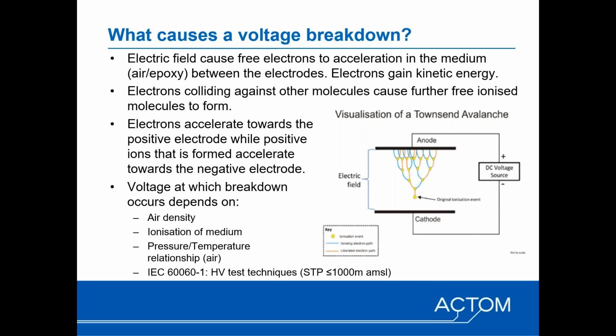Another factor that influences the voltage breakdown is the ionization of the medium. Some dielectric materials have a stronger bond to the electrons in the electron structure, so you require a higher voltage to release those electrons from the dielectric medium. Another factor is pressure and temperature, and the high voltage test standard for high voltage test techniques defines standard pressure for altitudes less than 1,000 meters above mean sea level. So when you apply or review insulation at altitudes above that, you need to apply certain correction factors to the applied voltage or the test voltage that you use. You either need to reduce the test voltage, or you need to increase the insulation that you require at higher altitudes.